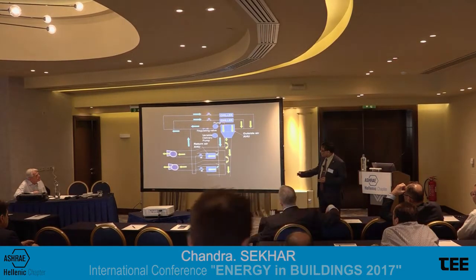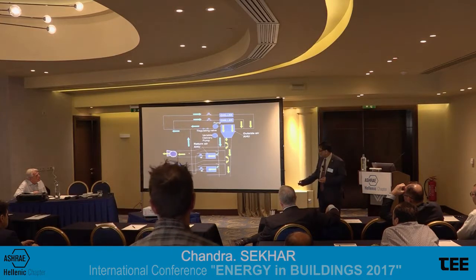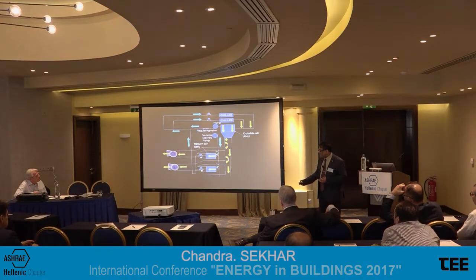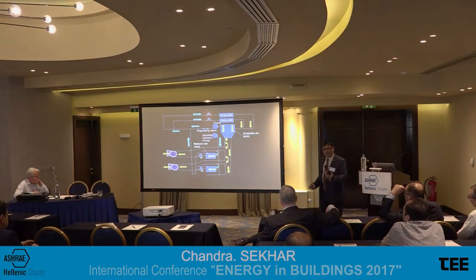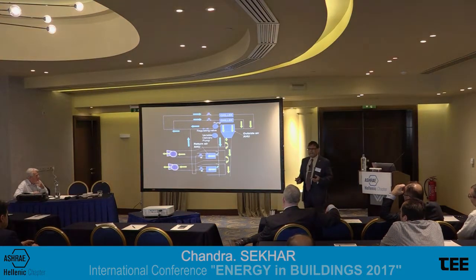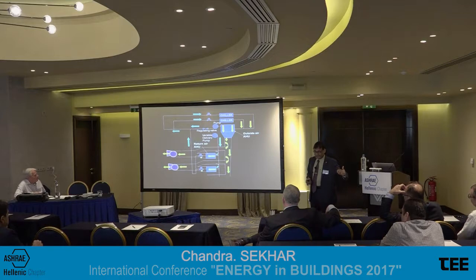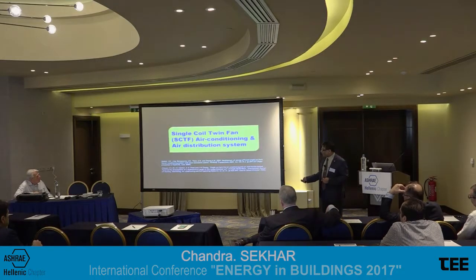at the rooftop doing the complete cooling and dehumidification, and we mix that after the floor air handling unit. In other words, the floor level AHU pretty much becomes like a sensible cooling air handling unit. Decoupled entirely, not like the one I described earlier, where it doesn't do a complete job.